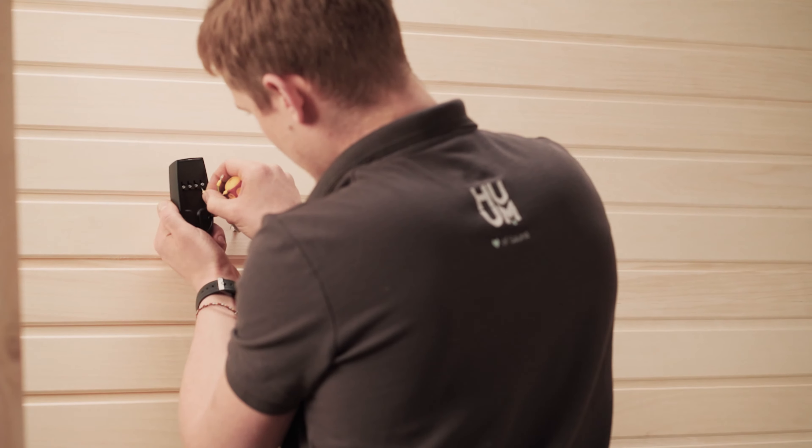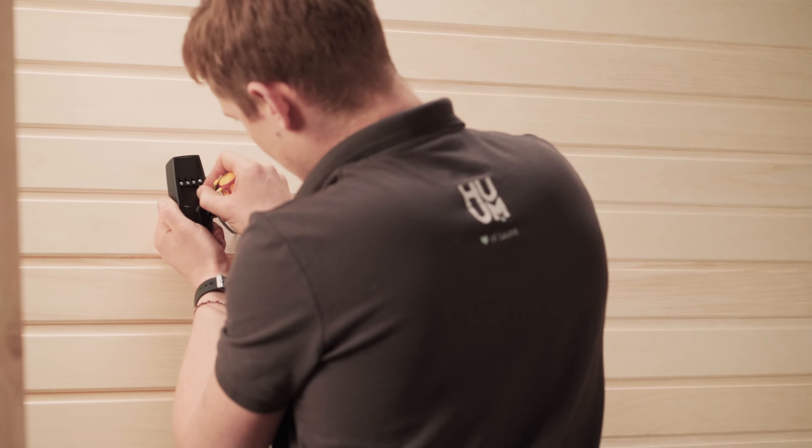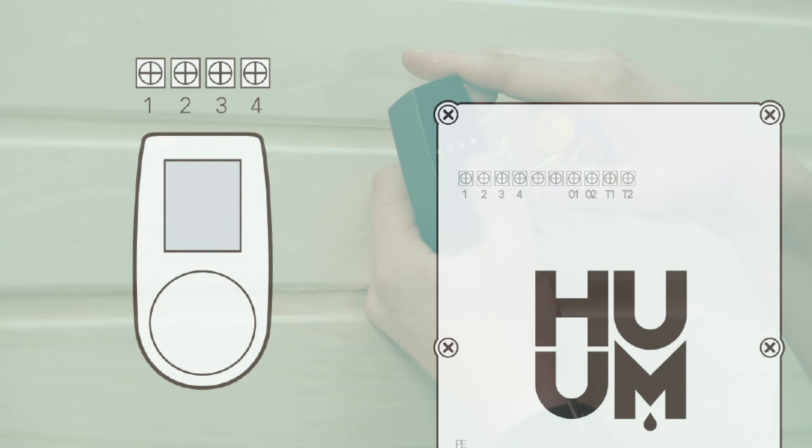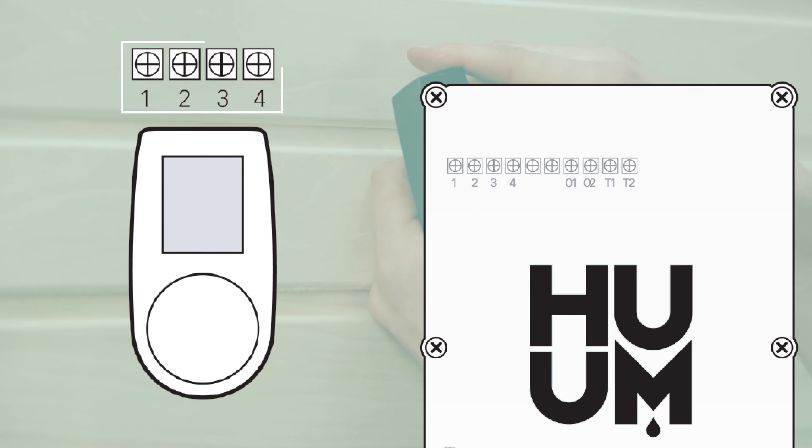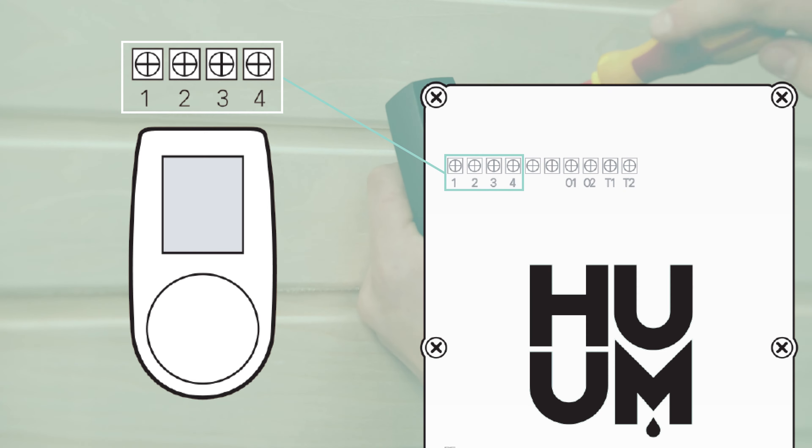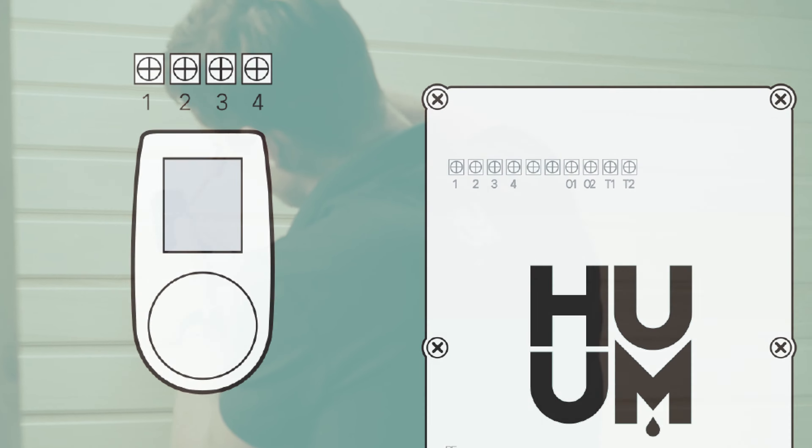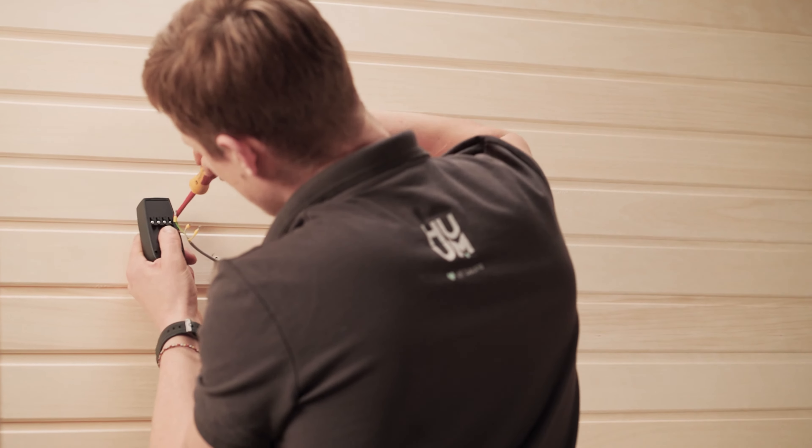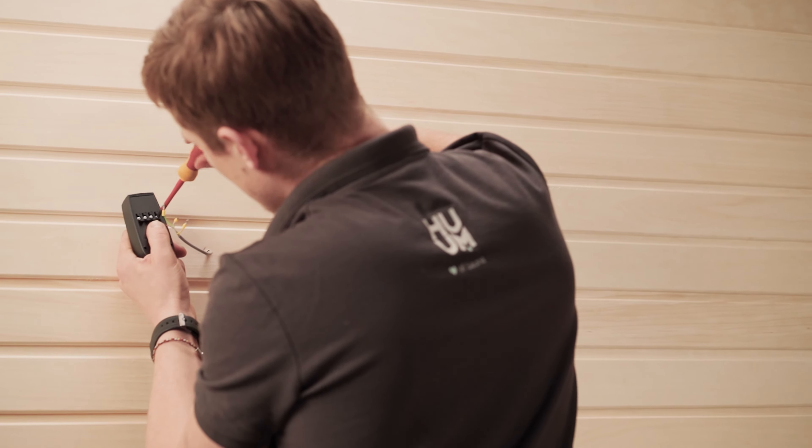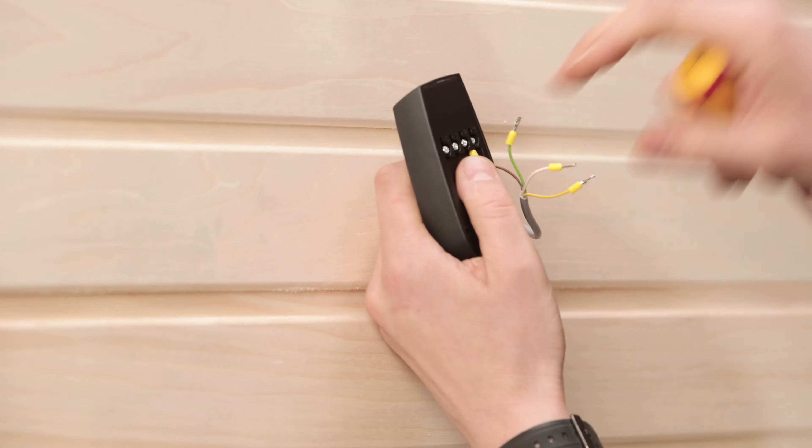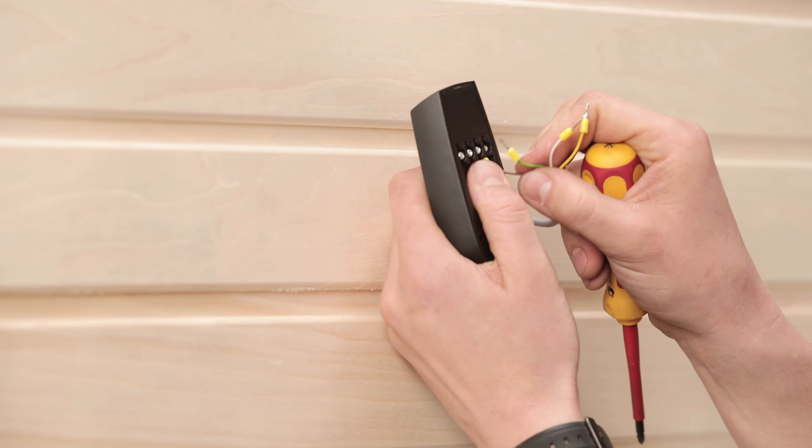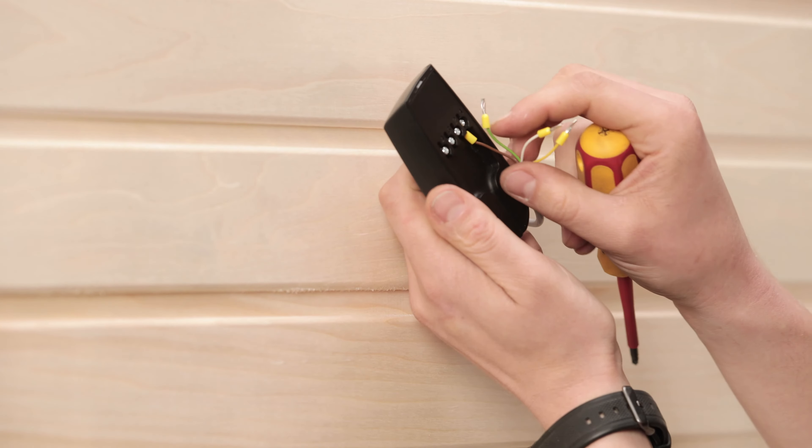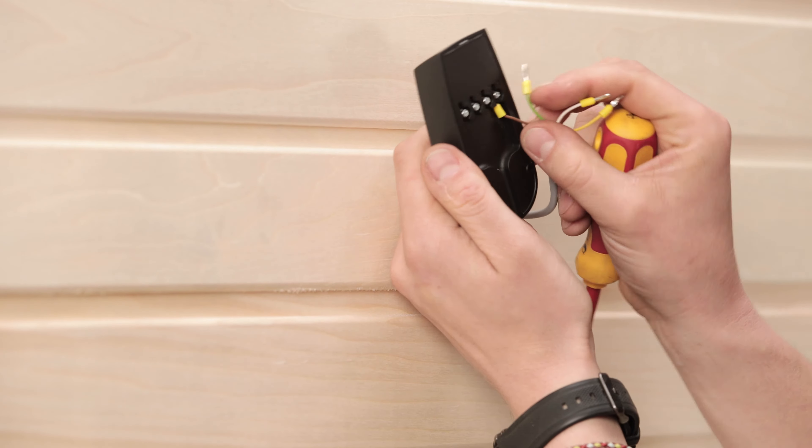You need to secure the wires to your wall-mounted controller. Just make sure you carefully match up the right numbered cables here. This is the most common source of the problem when people think their heaters might not be working. In some controllers, for example, the numbers run backwards, which some people don't notice. This work is a little bit fiddly, but we've added these wire sleeves to help.